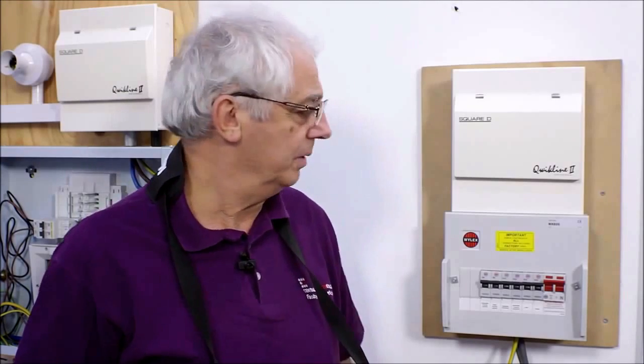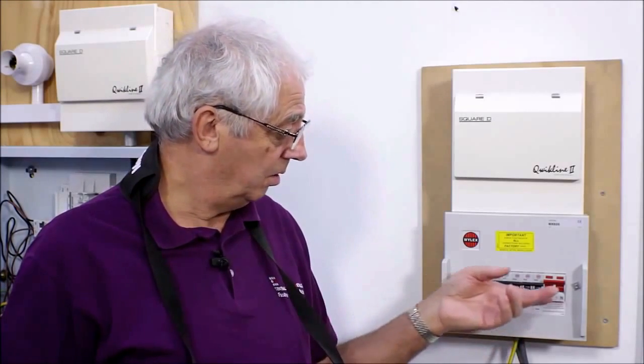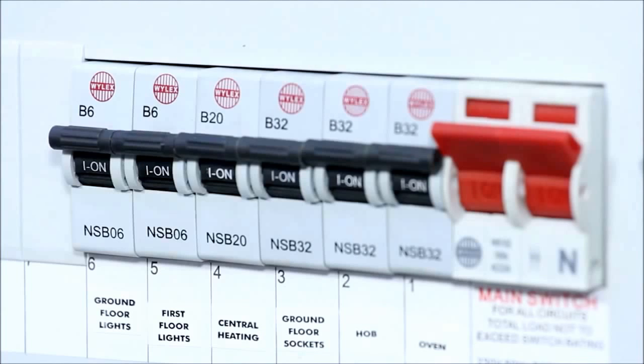Part of the inspection and testing process for an initial verification is an insulation resistance test. Here, we're going to carry out an insulation resistance test on the complete installation before the tails are connected. What we need to do is make sure that all of the circuit breakers are turned on, the main switch is turned on.